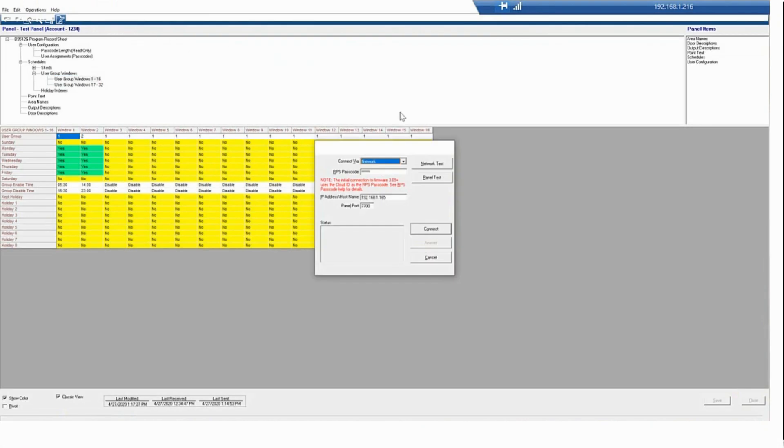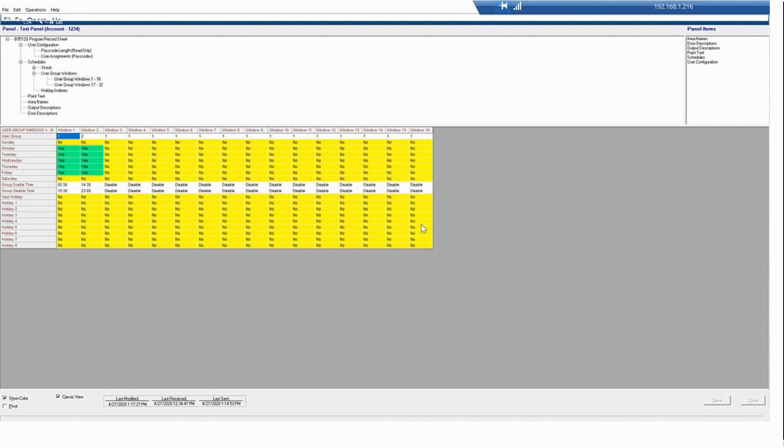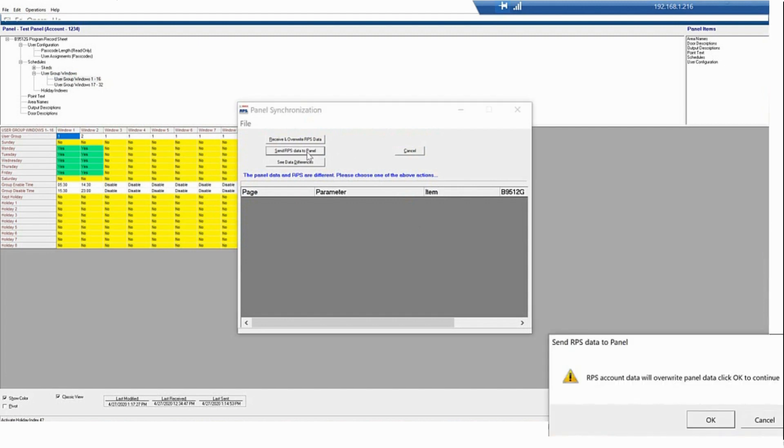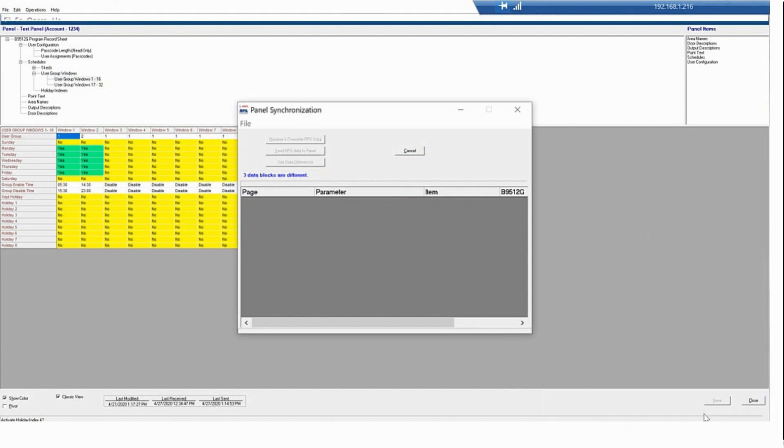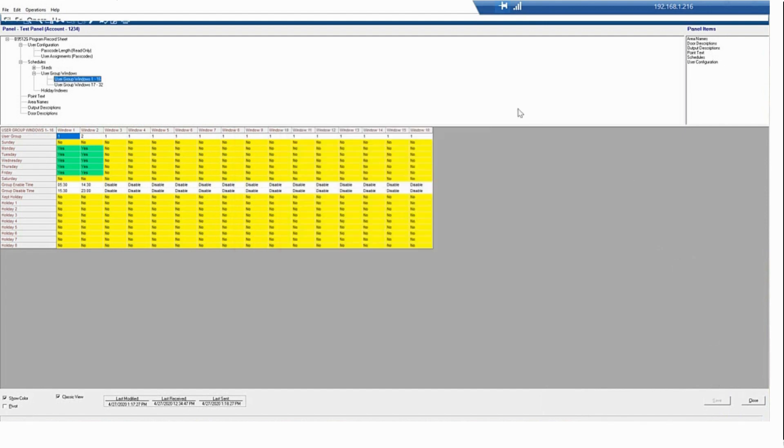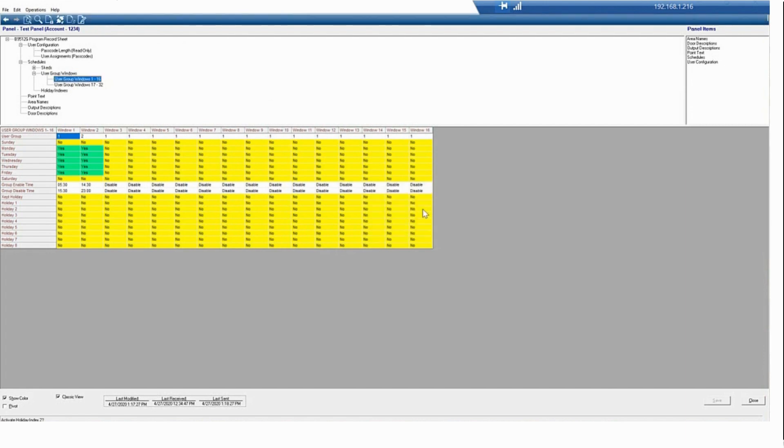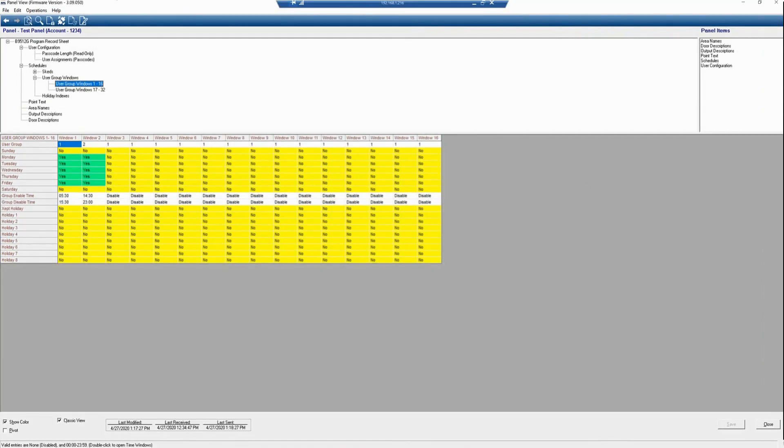Next, we're going to connect to the panel. We want to click Send RPS Data to Panel. All of the changes that we just made will now be sent to the panel. Now, we want to hang up our connection. Before we do that, we want to click Reset Panel, and then click OK. Resetting the panel will make sure that all changes take effect as soon as the panel is reset.